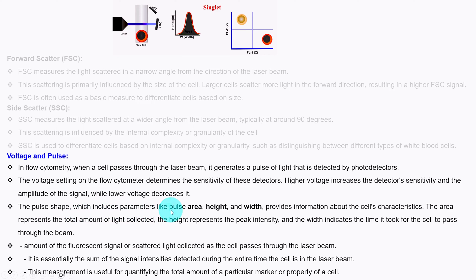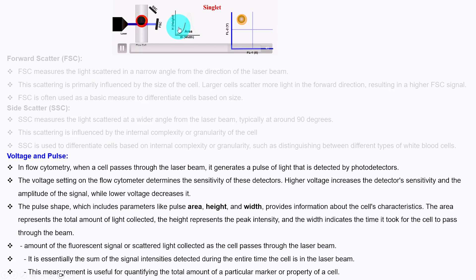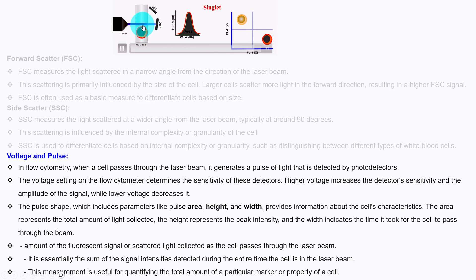These pulse parameters provide information about the cell's characteristics. The area represents the total amount of light collected. The height represents the peak intensity. The width indicates the time it took for the cell to pass through the beam. Width is the time taken to cross through the laser beam and height is the maximum signal when the cell crosses through the laser beam.